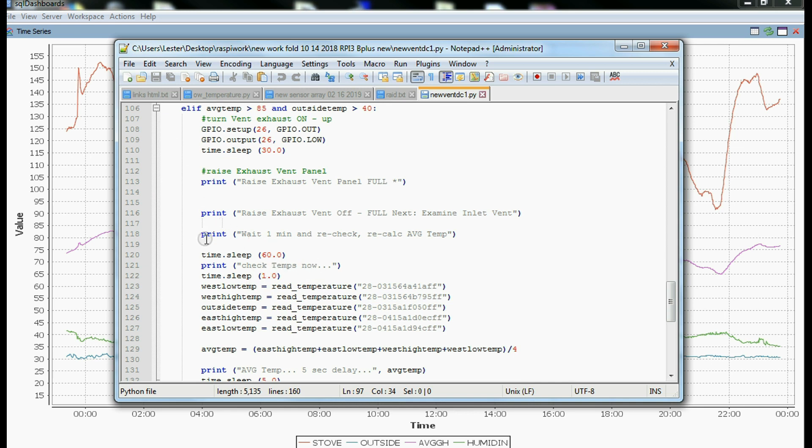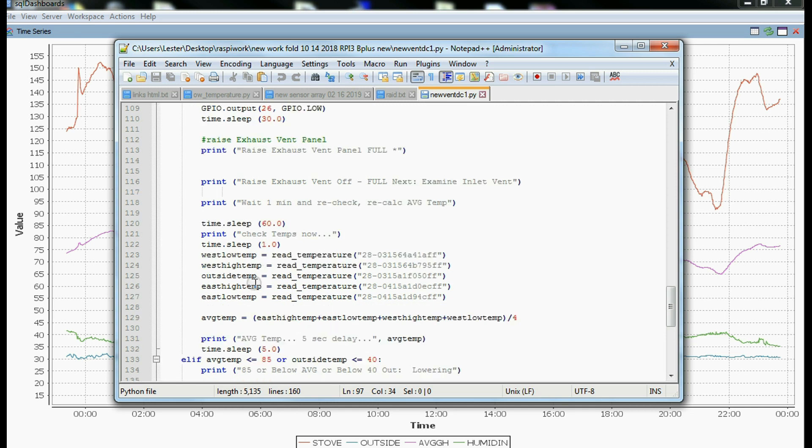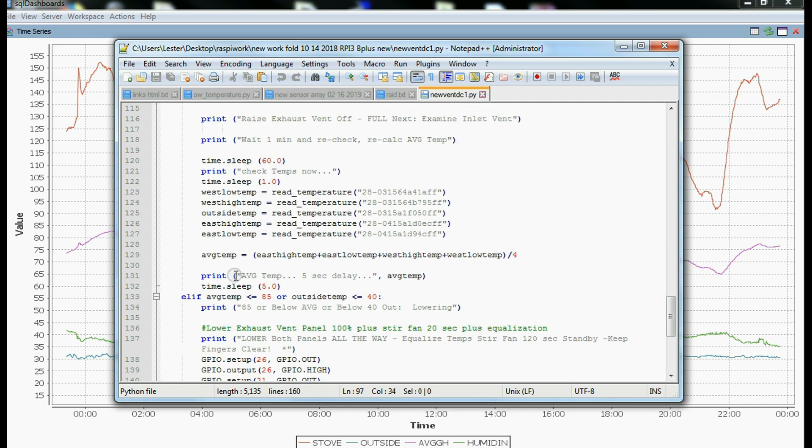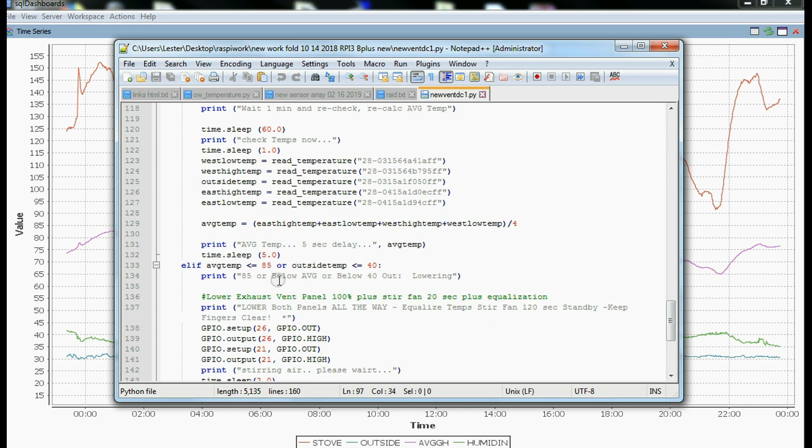So you see we raise the vent all the way, and we wait. And then in 60 seconds, we go back and we grab temperatures again. And we crunch the average, and we see if the average is above or below our set limit still. And if it's below our set limit, then we drop the vent. And if it's above, then the vent stays open.